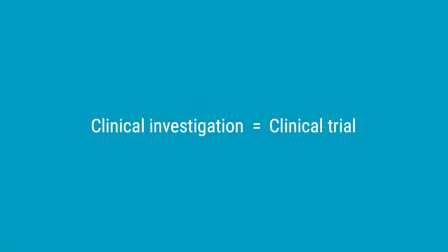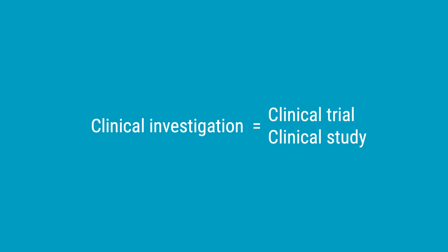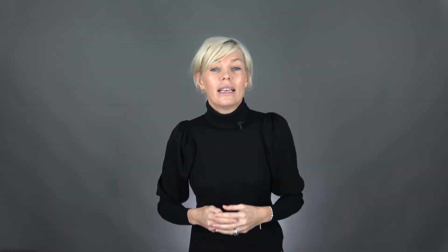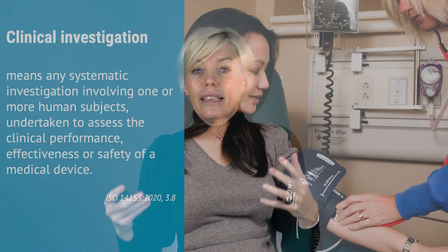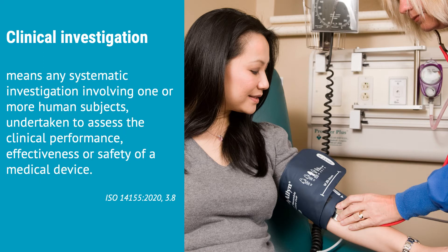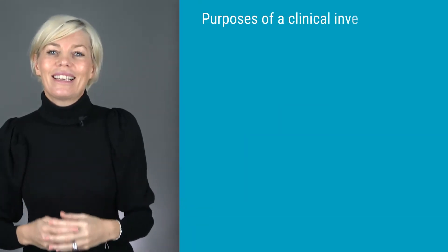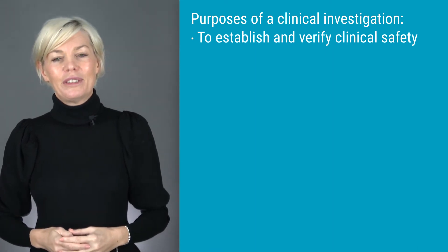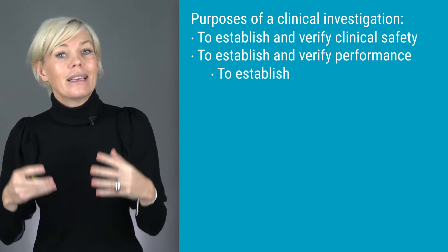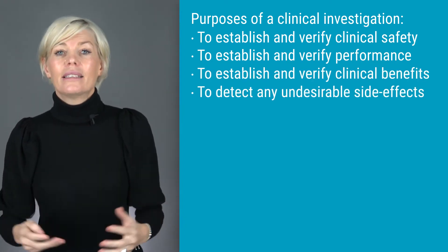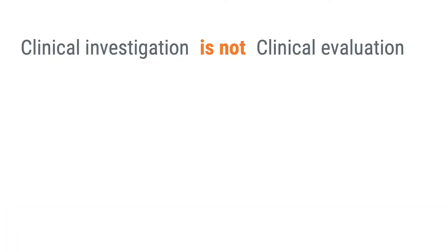In the ISO 14155 standard, the term clinical trial or clinical study are synonymous with clinical investigation. Clinical investigations are carried out to assess what works and does not work as treatment in humans. More formally, the ISO 14155 defines a clinical investigation as any systematic investigation involving one or more human subjects undertaken to assess the clinical performance, effectiveness, or safety of a medical device. The purpose is to establish and verify clinical safety, performance, clinical benefits, or detect undesirable side effects. It's important not to confuse clinical investigation with the term clinical evaluation.